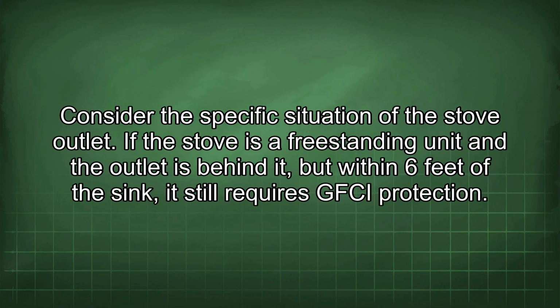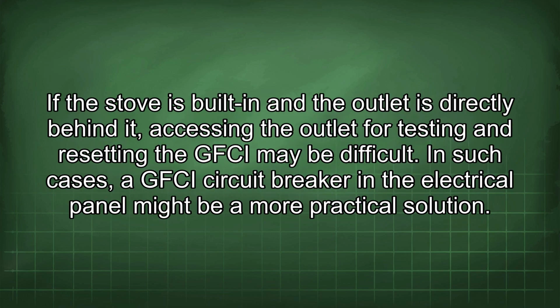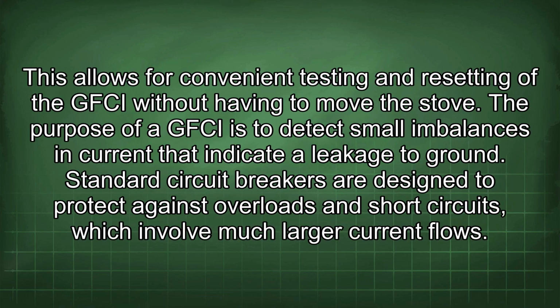Consider the specific situation of the stove outlet. If the stove is a freestanding unit and the outlet is behind it, but within 6 feet of the sink, it still requires GFCI protection. If the stove is built in and the outlet is directly behind it, accessing the outlet for testing and resetting the GFCI may be difficult. In such cases, a GFCI circuit breaker in the electrical panel might be a more practical solution. This allows for convenient testing and resetting of the GFCI without having to move the stove.